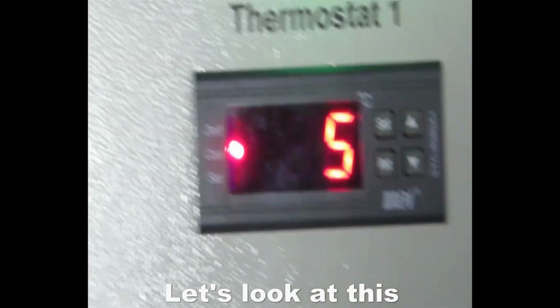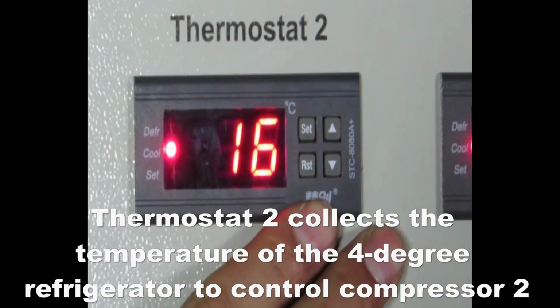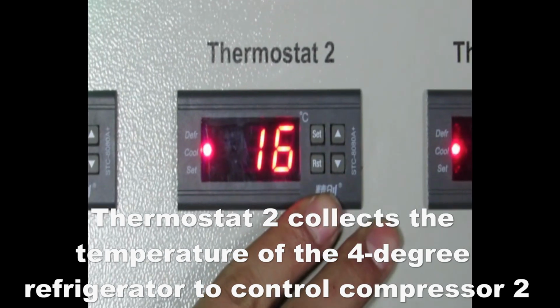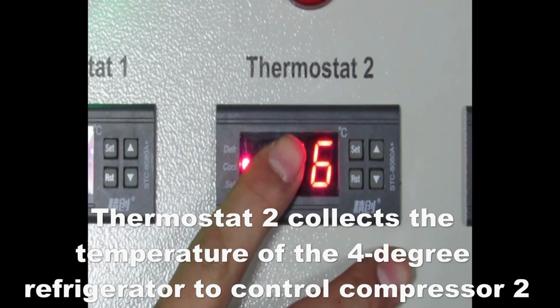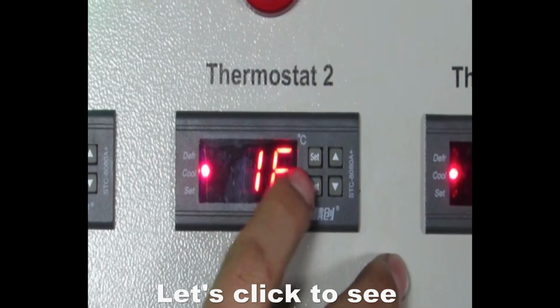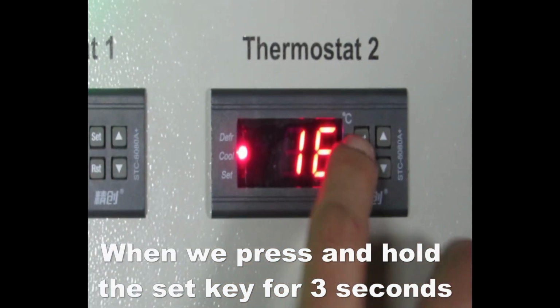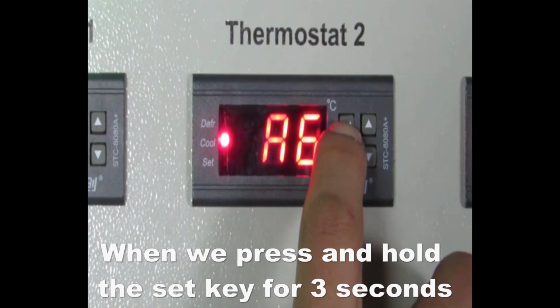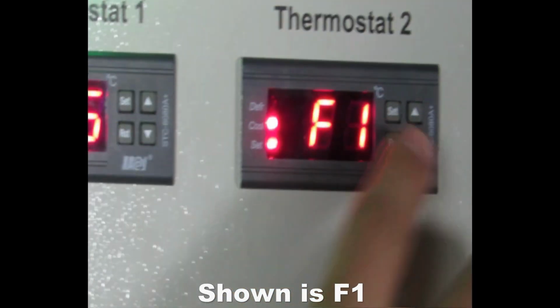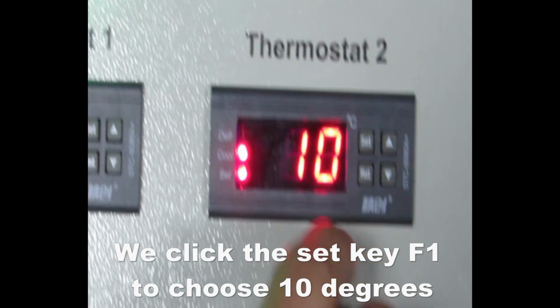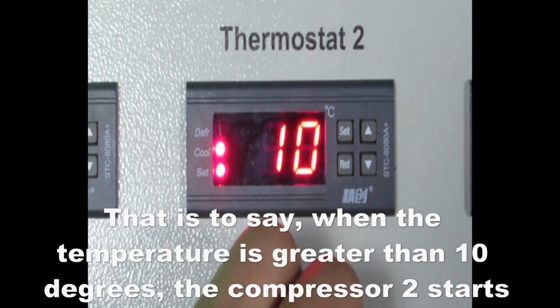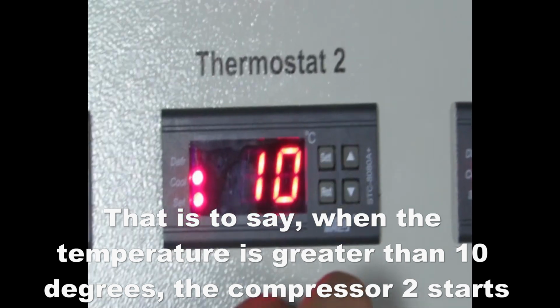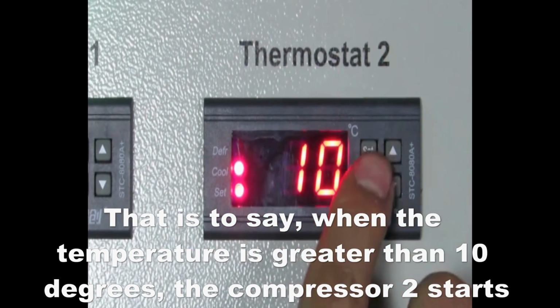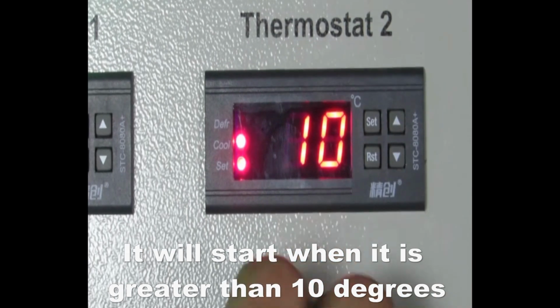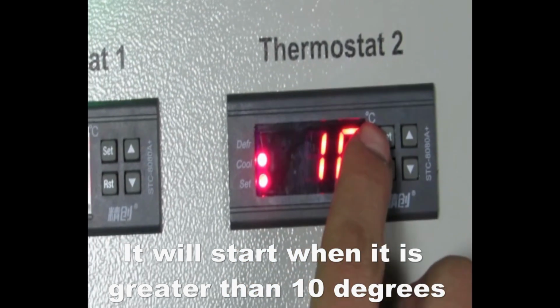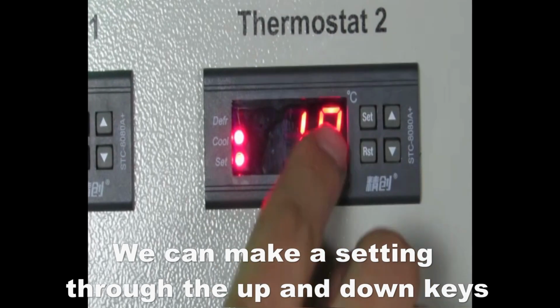Let's look at thermostat 2, which controls the 4 degree refrigerator and compressor 2. Let's click to see. When we press and hold the set key for 3 seconds, it shows F1. We click the set key and F1 is 10 degrees. That is to say, when the temperature is greater than 10 degrees, compressor 2 starts. We can make settings through the up and down keys.